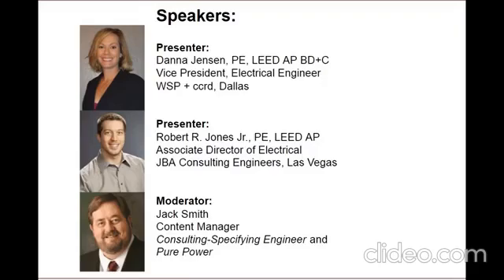Not applicable only to hospitals, but it certainly affects hospitals: they added an arc flash reduction requirement in NEC 2014, so you need to be aware of that because it affects hospitals as well as other buildings. They put in a definition of wet procedure location. Rob touched on that, but in NFPA now, ORs are defined as a wet location unless a risk assessment is performed. And something else that's kind of cool is NFPA 99 now allows fuel cells to be an acceptable alternate source of power in addition to the generator.